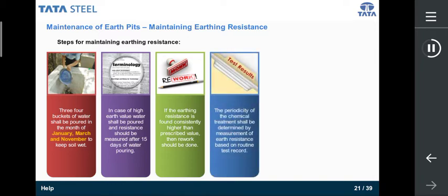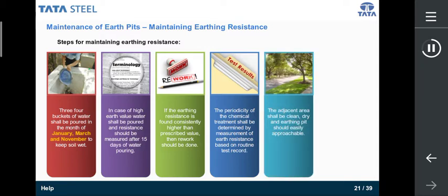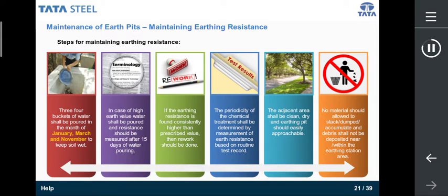The periodicity of chemical treatment shall be determined by measurement of earth resistance based on routine test record. The adjacent area shall be clean, dry, and the earthing pit should be easily approachable. No material should be allowed to stack, dump, or accumulate, and debris shall not be deposited near or within the earthing station area. That was the end of this topic. Time now for a quick review.